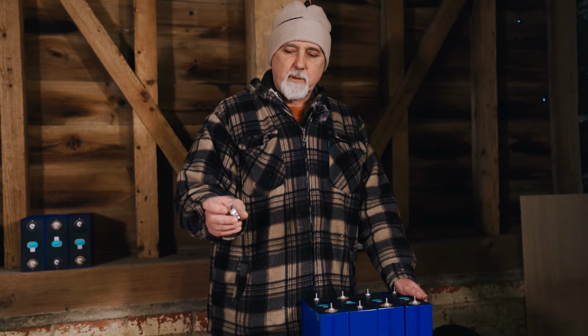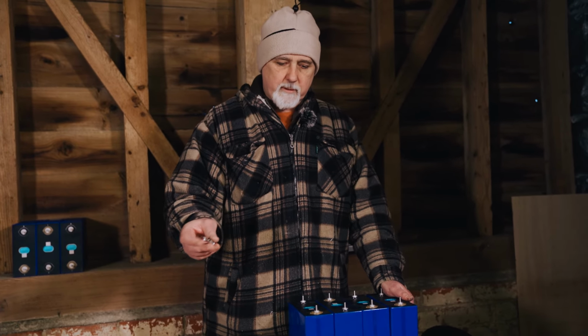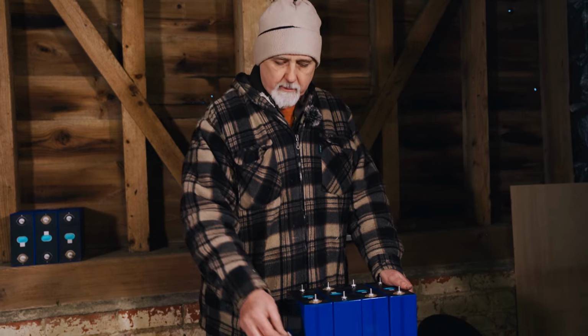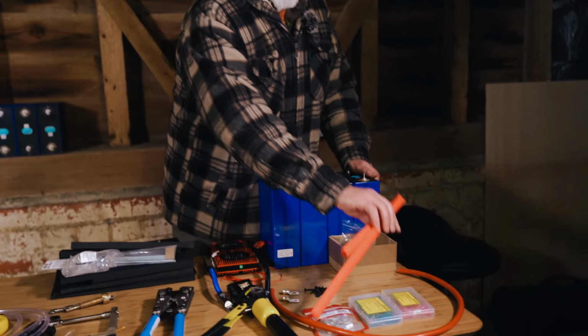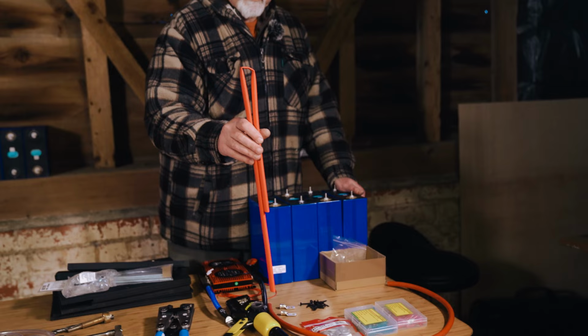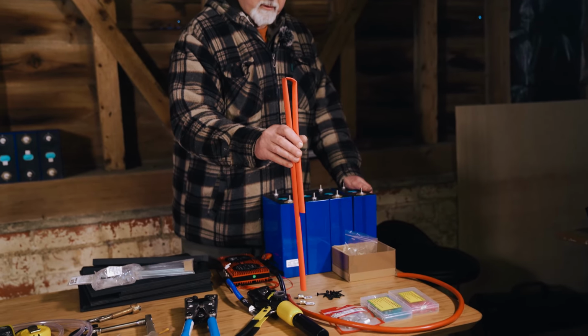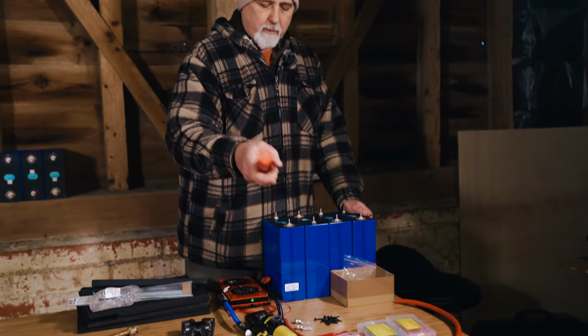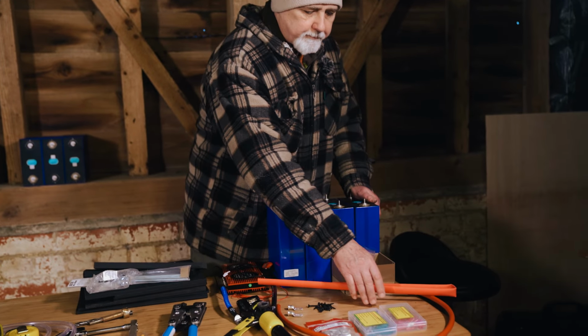We've chosen an 8mm because quite often that's what most of the bus bars are that you go to. You probably want some heat shrink - once you crimp the lug onto the cable, you're going to want to put some nice heat shrink on there.